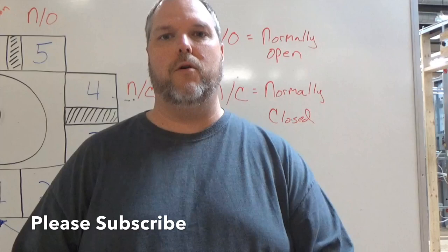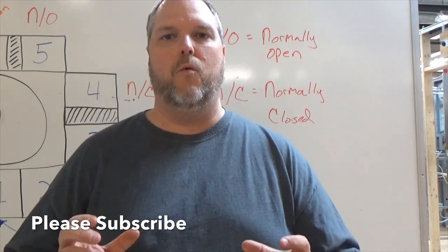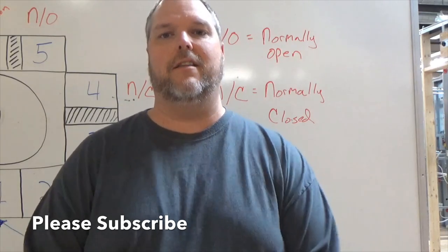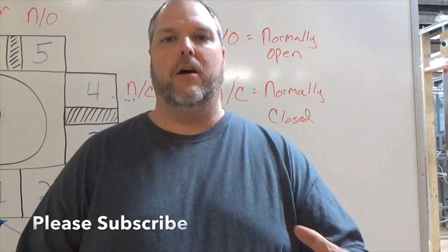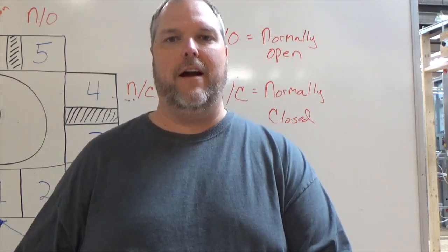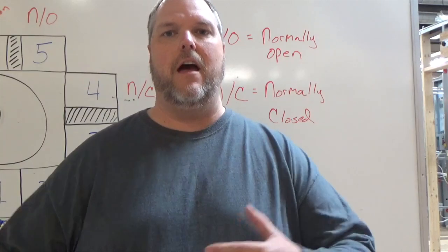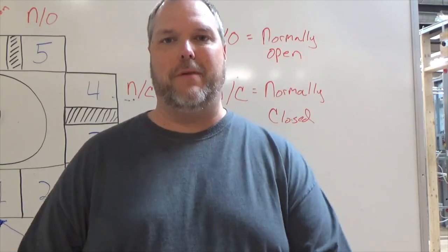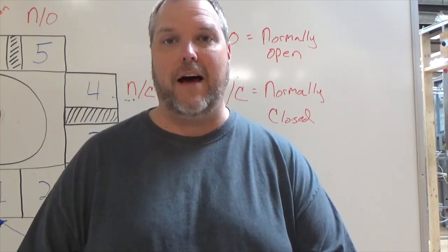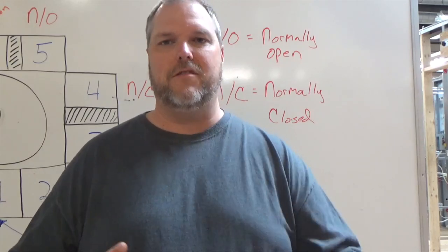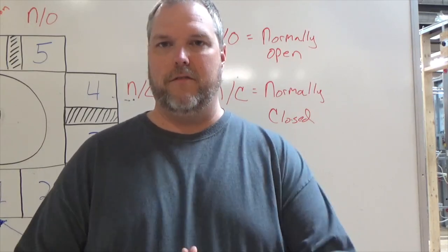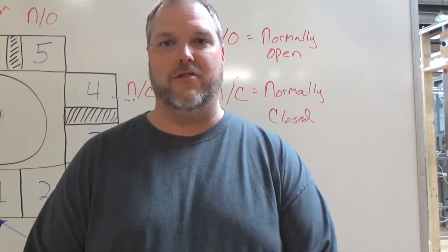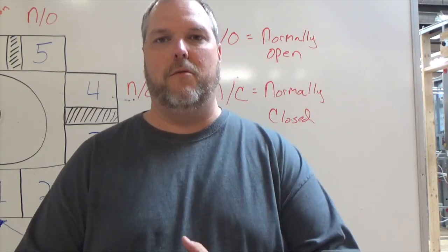The one thing you have to remember, it's the most important thing you have to understand in a relay. We work in a de-energized state, so when you look at a drawing, a ladder diagram, things of that nature, you're going to start to see that we draw our ladder diagrams in a de-energized state and how we make them work is basically what they do. We have to be able to understand the logic behind it. This is why they call it sometimes ladder logic. You have to understand what's what. PLCs and things of that nature, we're not talking about. This is just basic relay. As long as you understand normally open, normally closed, we can move on.